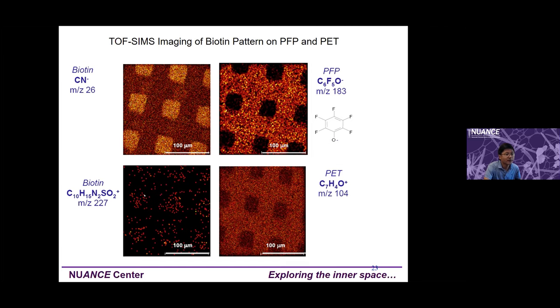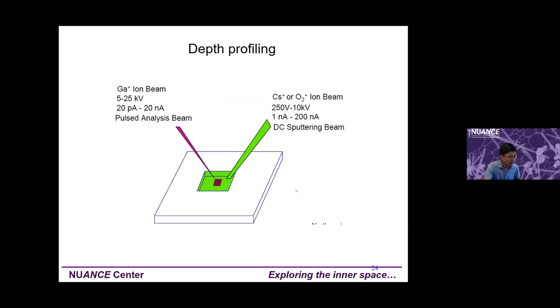Now about depth profiling. We use a gas sputter gun to make a crater, creating a new surface, and then use the primary ion analysis gun to analyze that surface. The sputter area must be much bigger than the analysis area, otherwise the analysis beam may be affected by the existing crater edge. So the gas gun creates the crater and the primary ion gun analyzes.